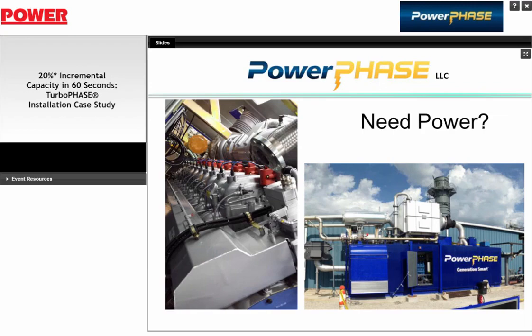But at this plant, our injection temperature was about 570 Fahrenheit, where the compressor discharge was like 650. On a 7FA, where things are maybe 100 degrees hotter, we would bump our temperature up into the 650 range. And yes, it is pretty much constant. It might fluctuate 5 or 10 degrees Fahrenheit, but it's pretty constant.